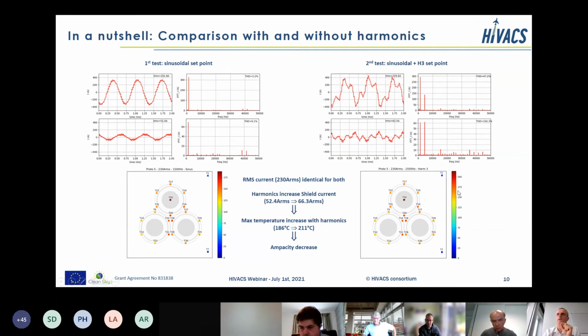And what I didn't explain very well is that by our control, we also regulate to have the same true RMS current in the two tests. It means that in this test or this test, what is circulating in the conductor is the same true RMS current, and we expect the same losses in the conductor. But there is not the same induced current in the shield, as you can see, the value 50 or 66 ampere. And so the impact is important on the temperature distribution, and in the configuration with more harmonics, there is a hotter temperature. It means that we have an ampacity decrease if we have a signal with a lot of harmonics.